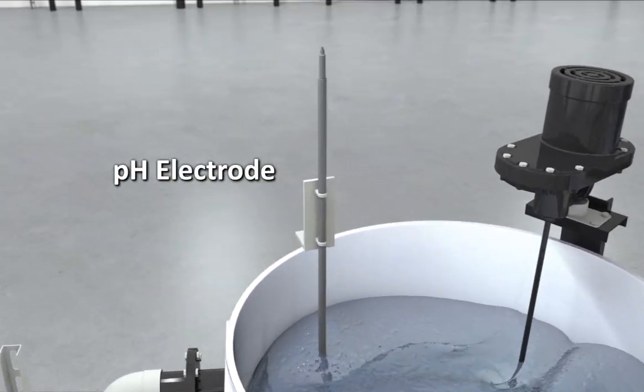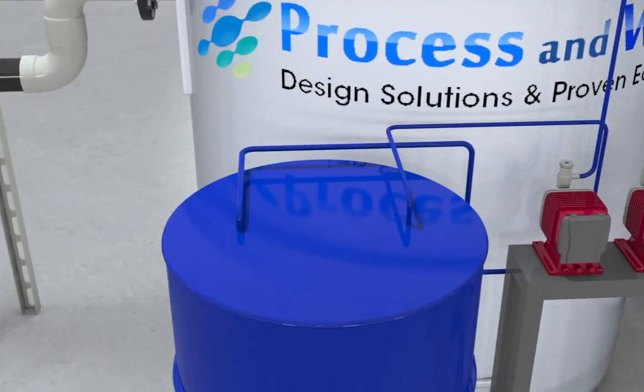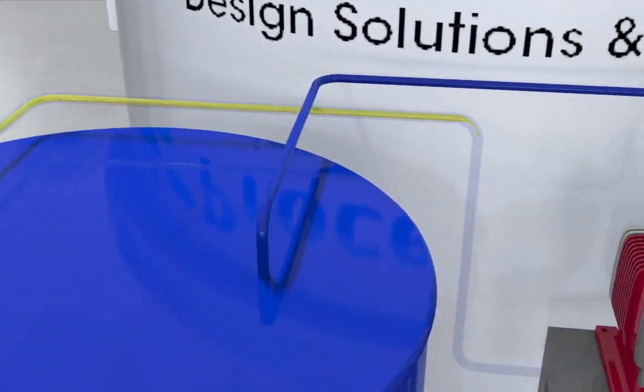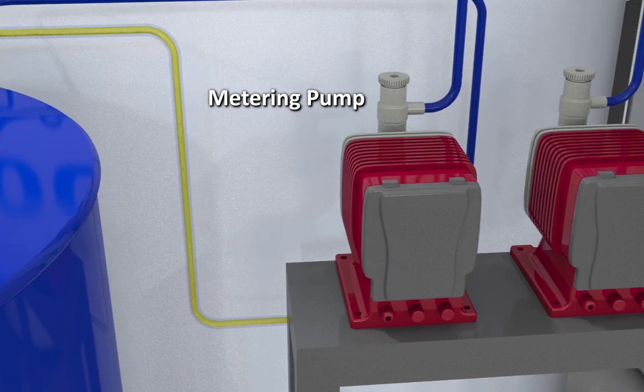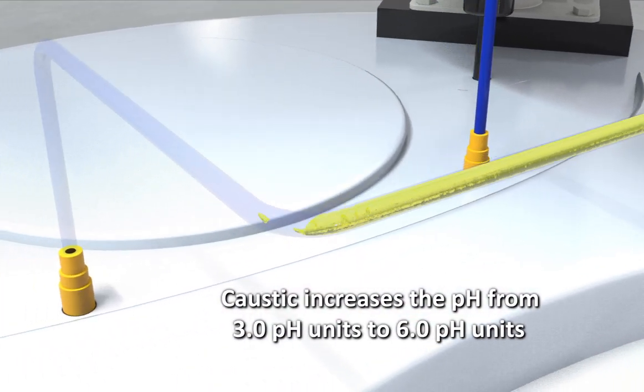The pH electrode senses the pH and displays the results on the control panel. The chemical metering pump dispenses caustic from the first chemical drum through the metering pump to the tank to increase the solution's pH from 3.0 pH units to 6.0 pH units.